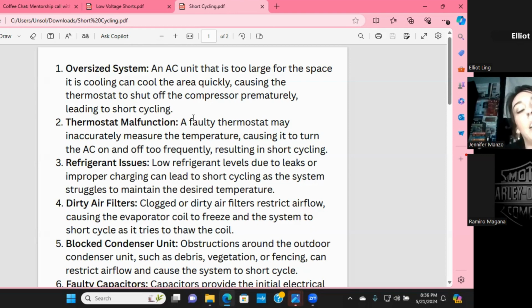So if we arrive at a system, whether it's for maintenance or a service call, and we notice that it's short cycling, we've got to do everything that we can to stop that from happening. Not only are they going to wear out their compressor, but other components too. Contactors and capacitors go far more often when we're getting that short cycle going on, because they're not built to do that. But here are some reasons.